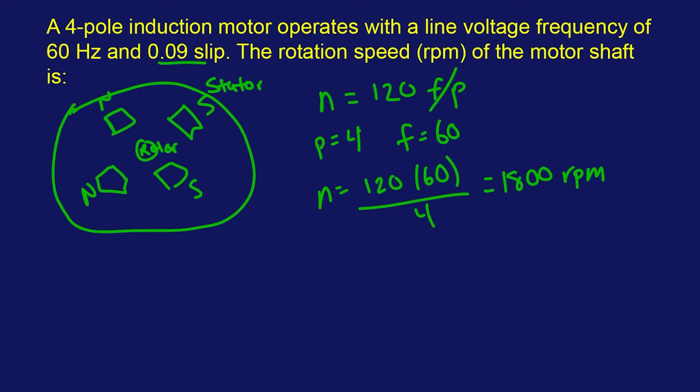So we're going to call the slip S equals 0.09. So this is very simple. This is the ideal scenario, or the synchronous speed of the motor. And we're trying to find the actual speed of the rotor. So let's say N minus NA. NA is for the actual, like what you're actually going to see, over the synchronous speed, which is N. And then this is going to be your slip.